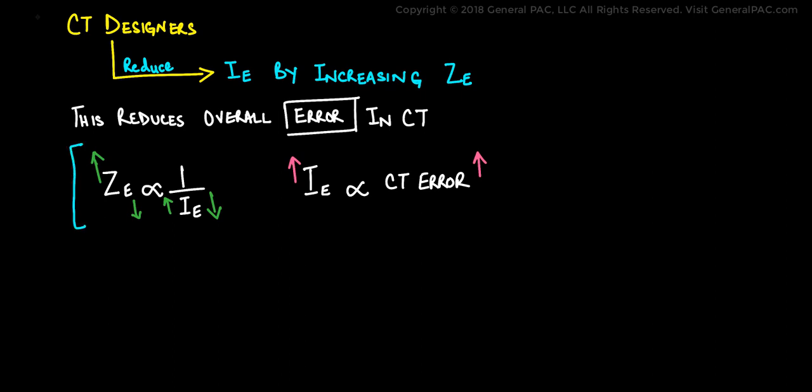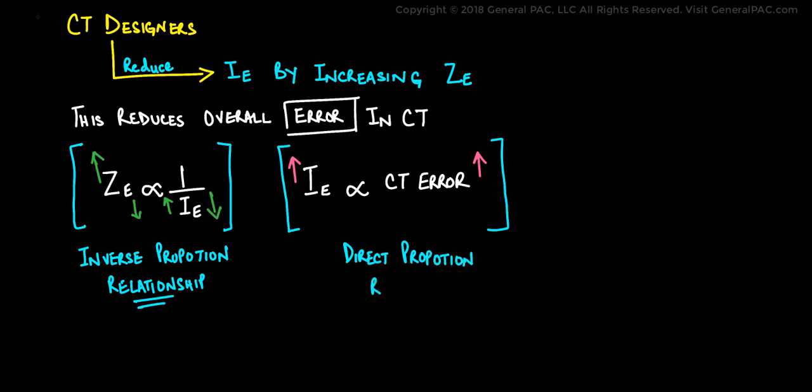Now how will we represent this mathematically? Well that is very simple. ZE is proportional to one over IE. So this is an inverse proportional relationship. If one goes up, the other goes down and vice versa. And IE, the excitation current, is directly proportional to the CT error. So if one goes up, the other goes up. And if one goes down, the other goes down with it.